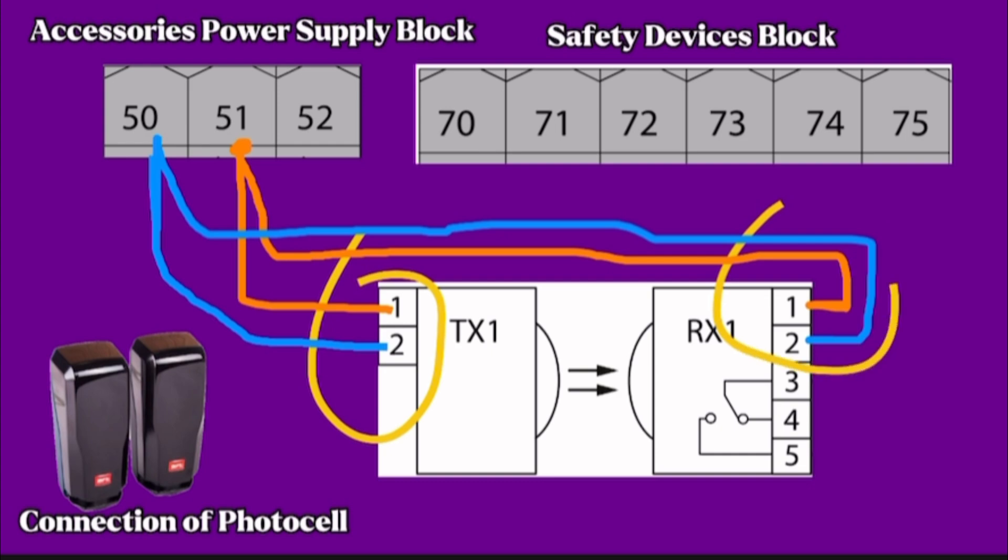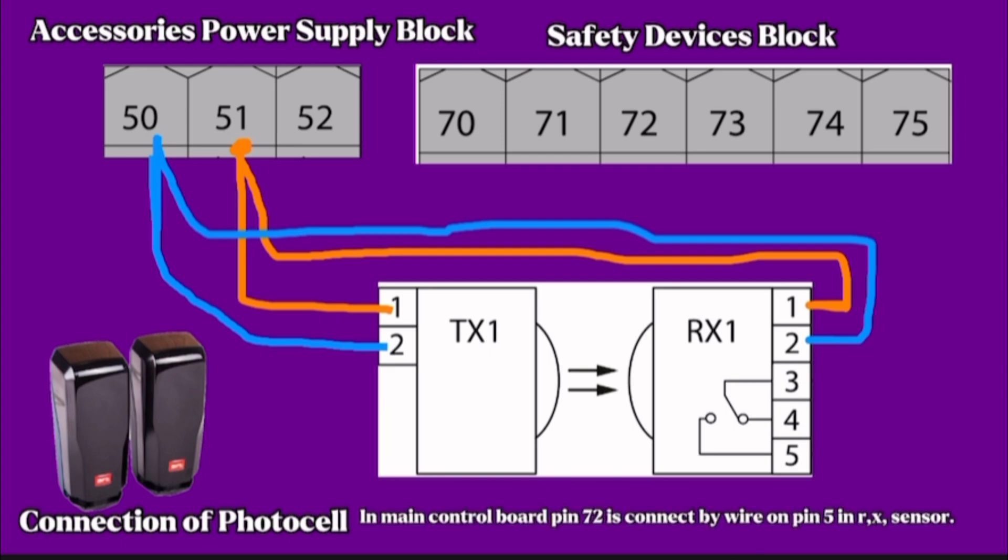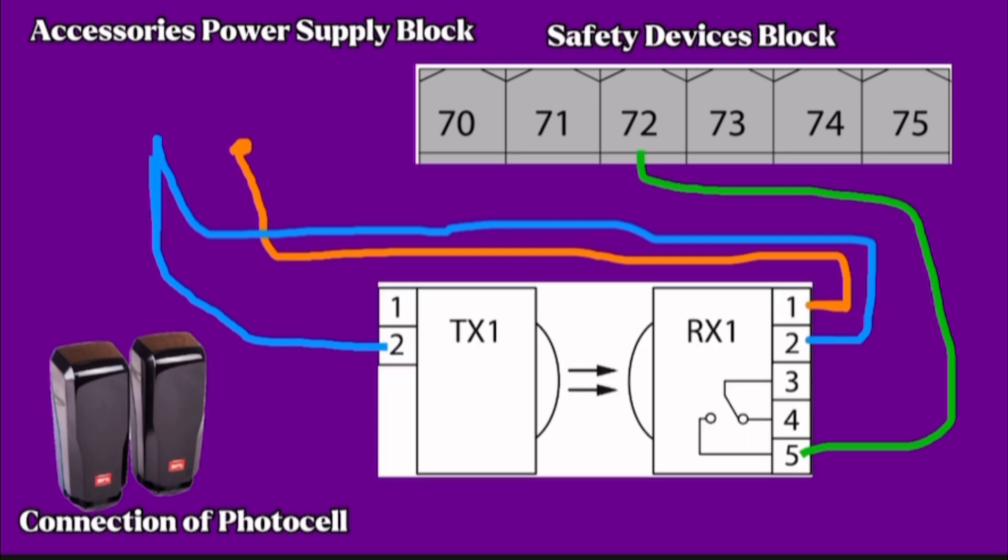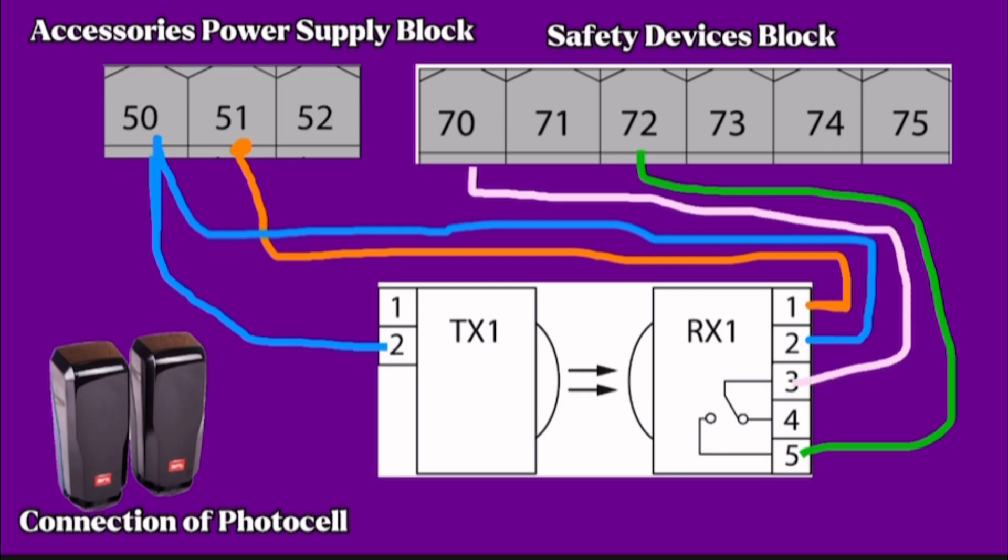In main control board, terminal 50 connects by wire to TX and RX pin 2. Now we have connected power supply of RX and TX. Pin 70 connects by wire on RX sensor pin 3. Pin 70 is common for this safety device block.